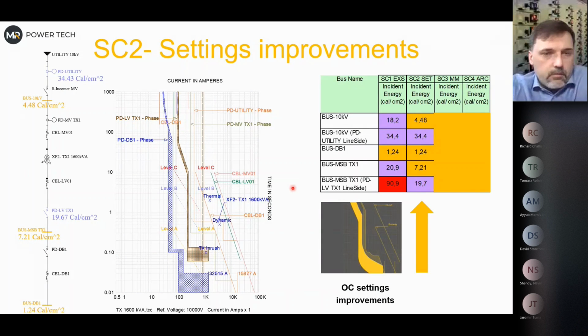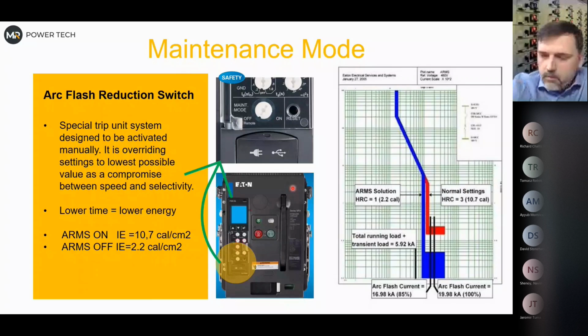So that's only when we play with the overcurrent settings. We play with what we have, and that's how far we can go, at least to this level. Probably we can tweak it a bit more, but that was, let's say, a reasonable level. Again, I spoke about the maintenance mode, the arc flash reduction switch, the energy reduction switch, and how it works.